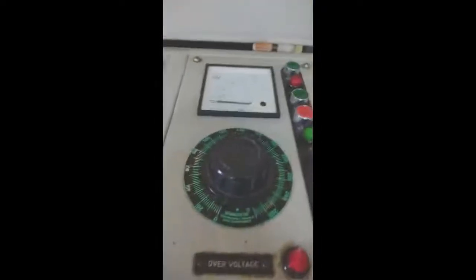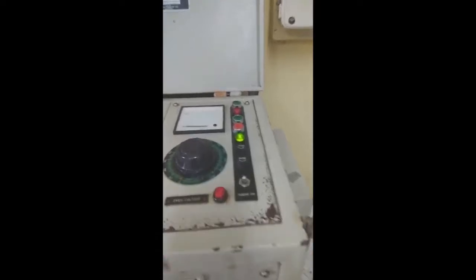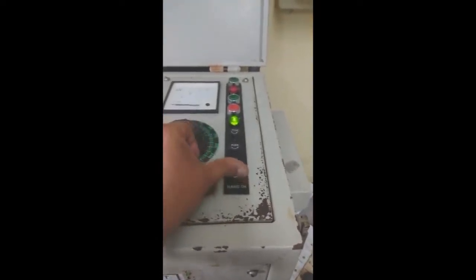You have to take this reading 6 times, and then you have to get an average of the last 5 readings. That is, the first reading will not be considered, because this is the idle position of the transformer oil. It was cooled, so we can't take the first reading. Then the next 5 readings will be averaged, and we can get the insulation or dielectric strength of this insulating oil. Okay, thank you.